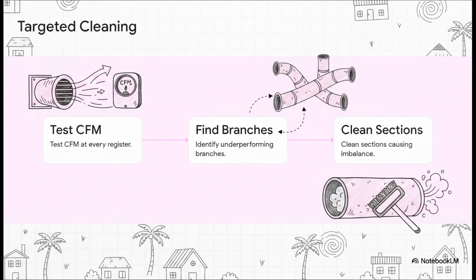We follow a very specific, almost surgical, three-step procedure to resolve this. First, we test the CFM at every single register in your home to create a complete airflow map. Second, we use that data to pinpoint the exact underperforming branches. And third, we clean and clear only the specific problem sections causing the imbalance.